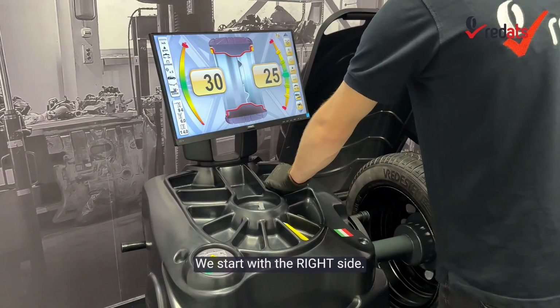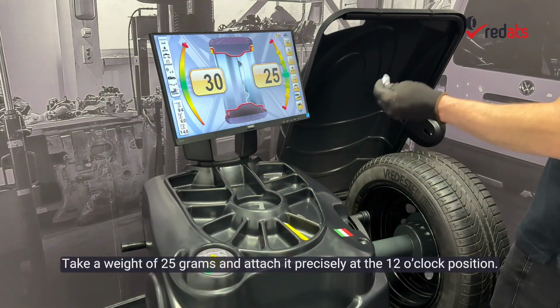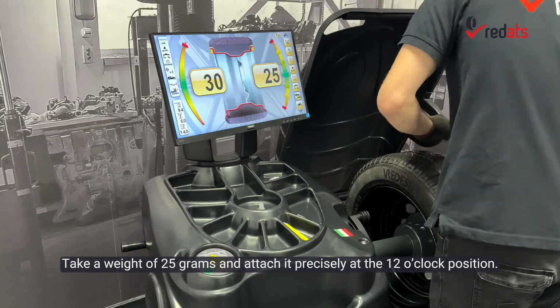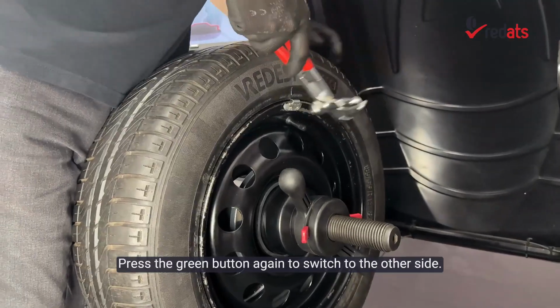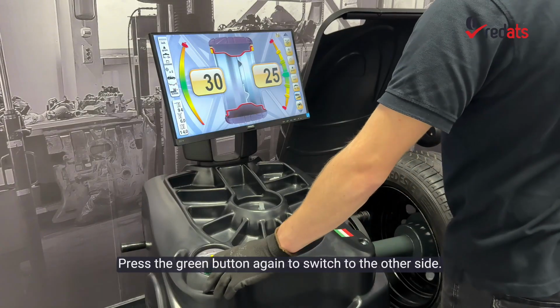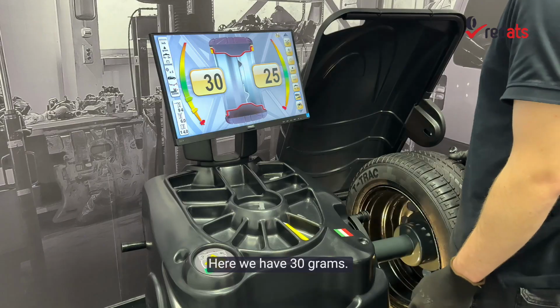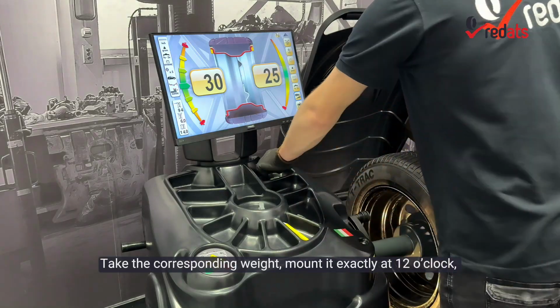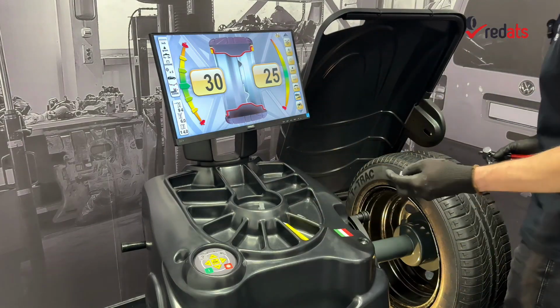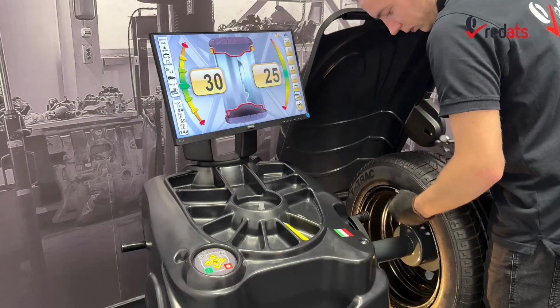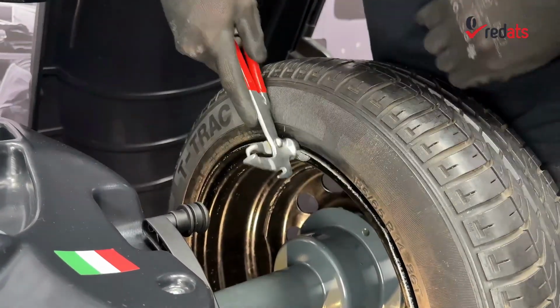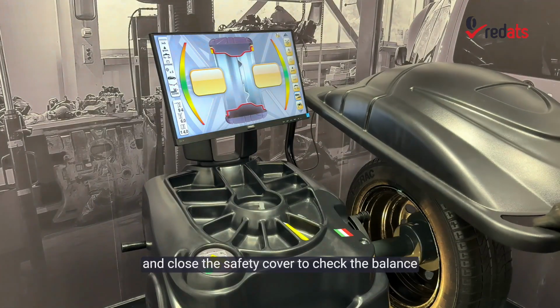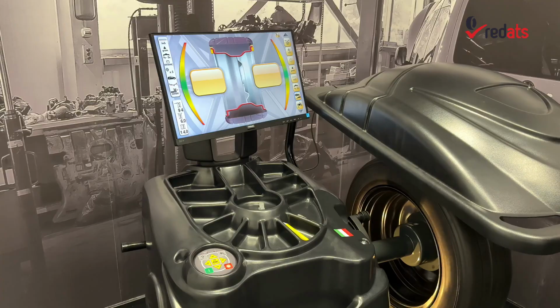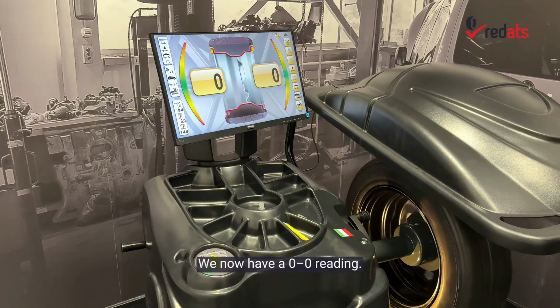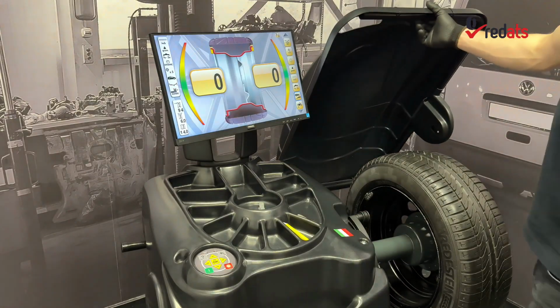We start with the right side. Take a weight of 25 grams and attach it precisely at the 12 o'clock position. Press the green button again to switch to the other side. Here we have 30 grams. Take the corresponding weight, mount it exactly at 12 o'clock, and close the safety cover to check the balance. We now have a 0-0 reading.